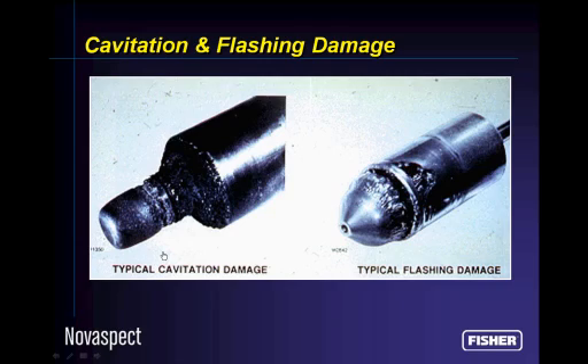And you would probably find, if you pulled the plug out of a valve and saw it look like the one on the left, you probably noted while the valve was in operation that it sounded like gravel running through the pipe. And that is the sound of cavitation, and we're going to talk about what exactly is cavitation here in a couple minutes.